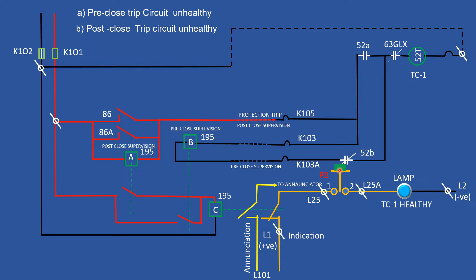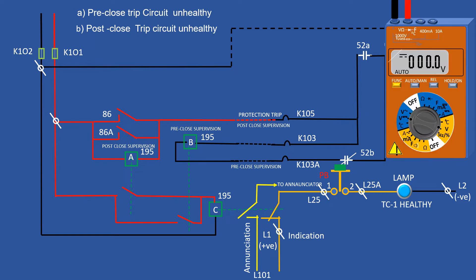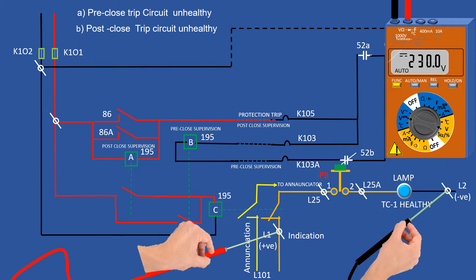Trip circuit unhealthy due to fault at indication circuit. Now we shall go through the process of checking. First of all, we check DC input. We shall take a suitable multimeter, keeping selector knob at DC volt position. Red hand lead of multimeter is kept at L1 DC positive and black hand lead at L2 DC negative. Multimeter reading will show 230 volt DC, that is DC is okay.